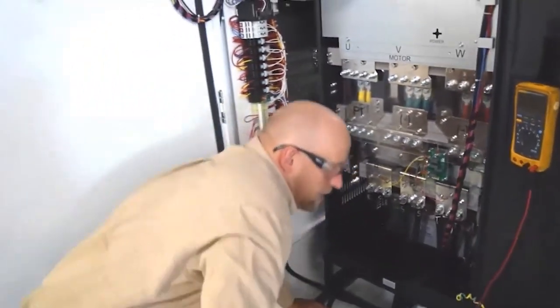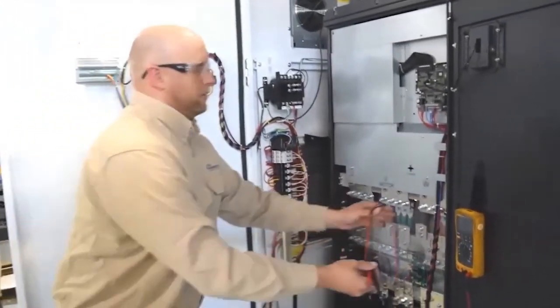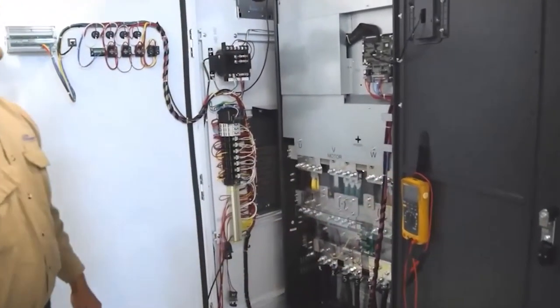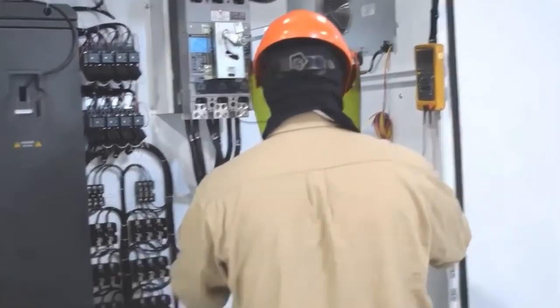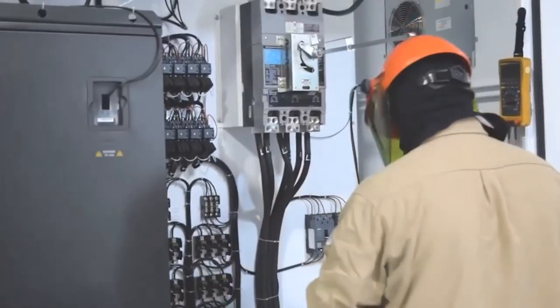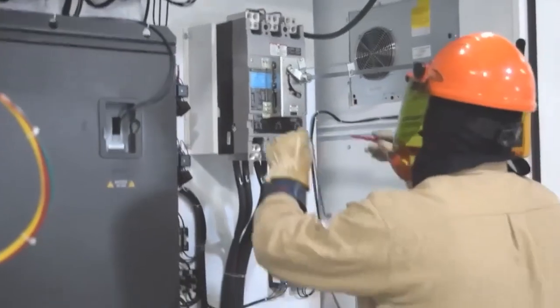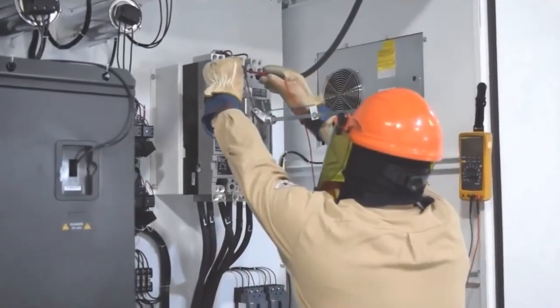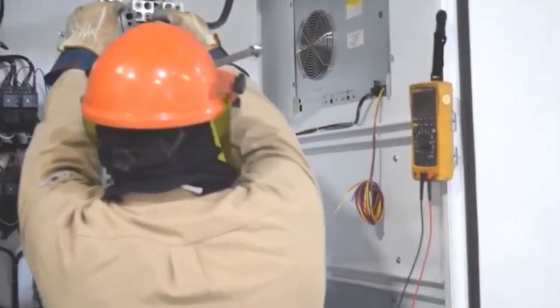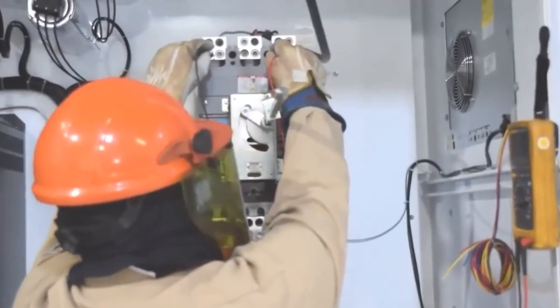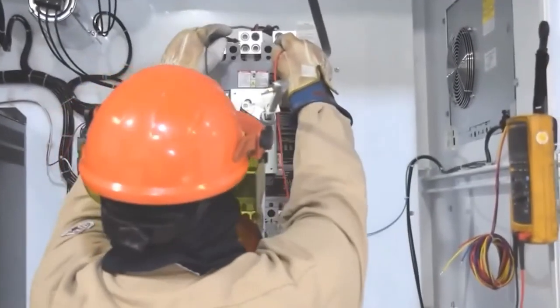And so that's how you do a static check on a drive. And all drives, you're going to be able to do a similar test. So sometimes it's a little harder to find the bus. So now what we're doing is I've put my PPE back on. We've energized the cabinet, and we're going to go ahead and do our energized testing.